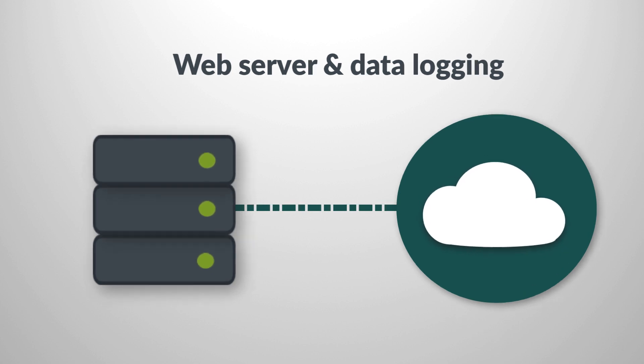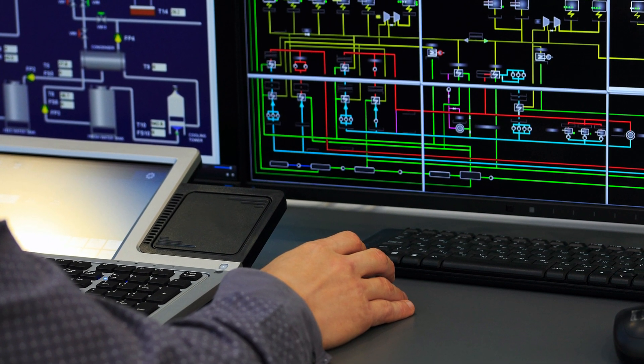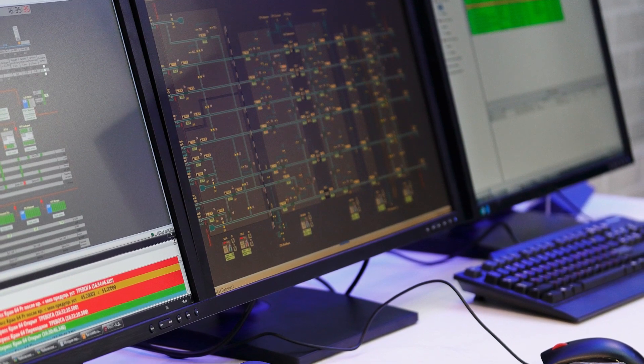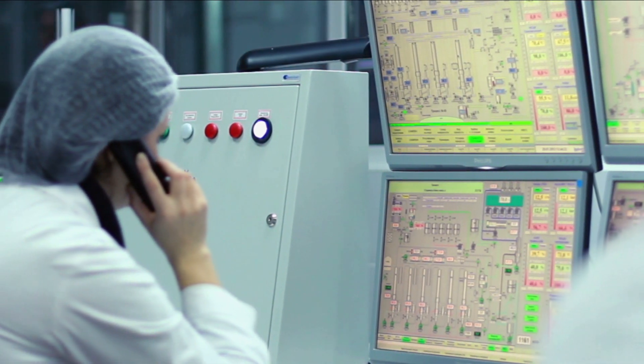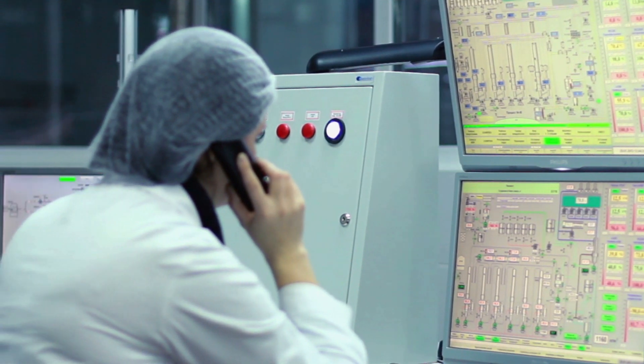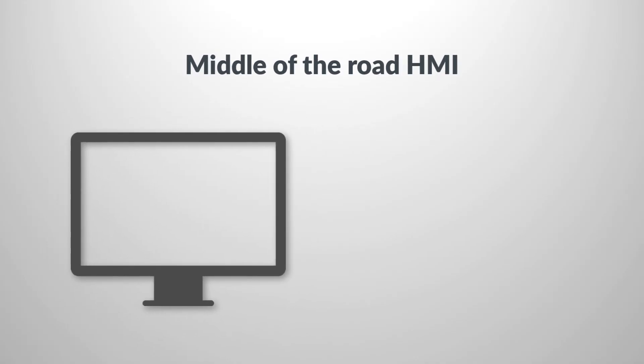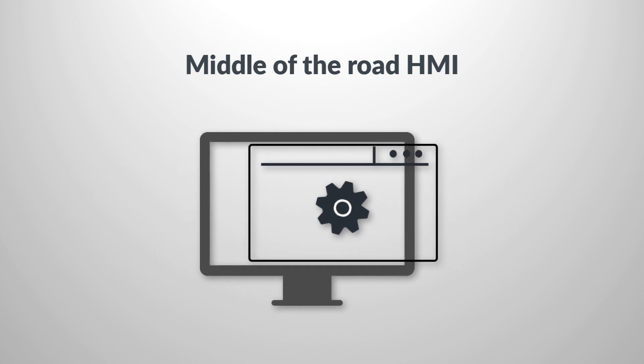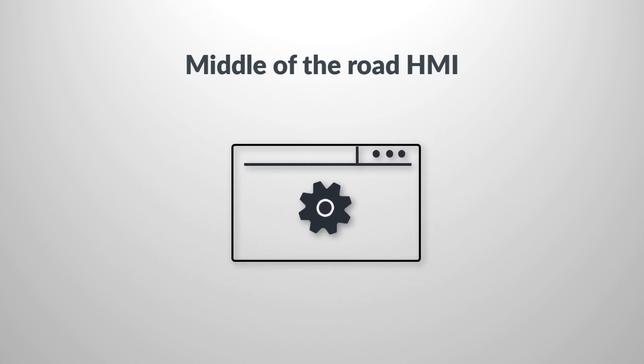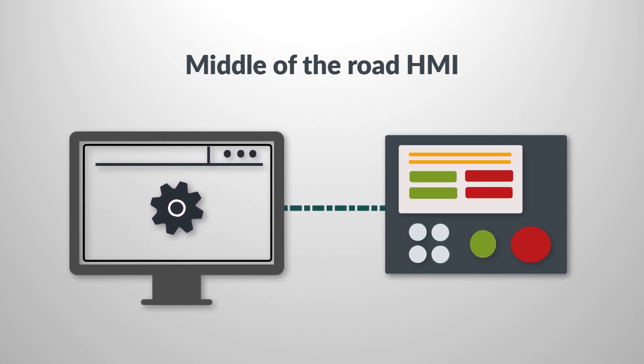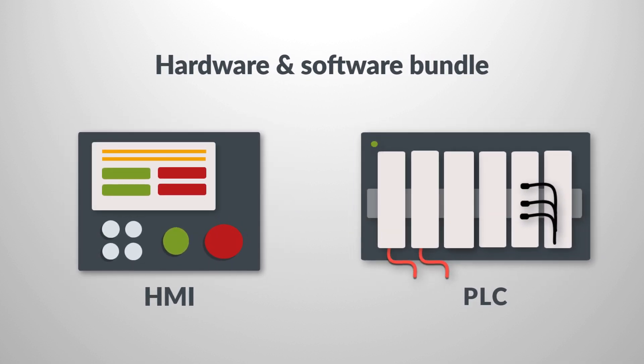As the machine application requirements move to more graphical screens, buttons, alarm history, recipe functions, trends, and historian functionality — such as those commonly offered by PLC vendors — HMI software functionality increases. These middle-of-the-road HMIs, usually embedded PCs, still closely tie the HMI hardware and software together. Typically, the software is configured and written on a development PC and then downloaded to the HMI, with each HMI including the runtime. With the HMI and PLC from the same vendor, the software for the HMI may use the same development platform as the PLC programming software.